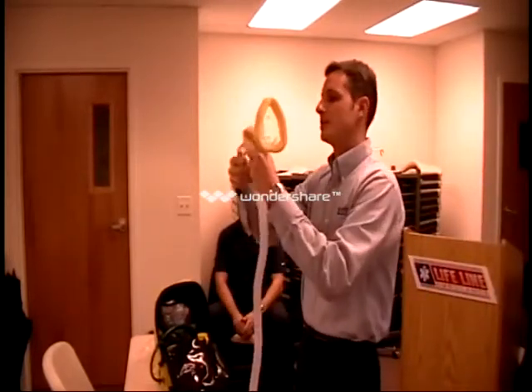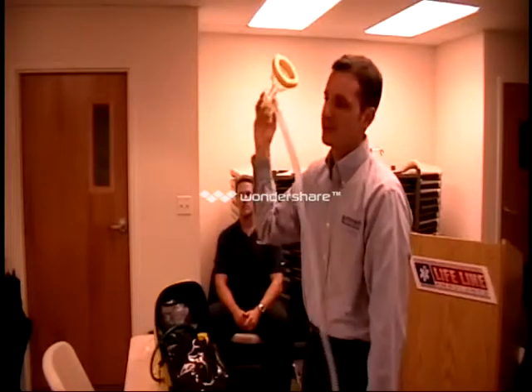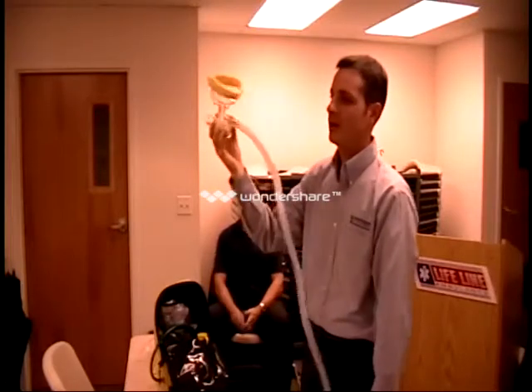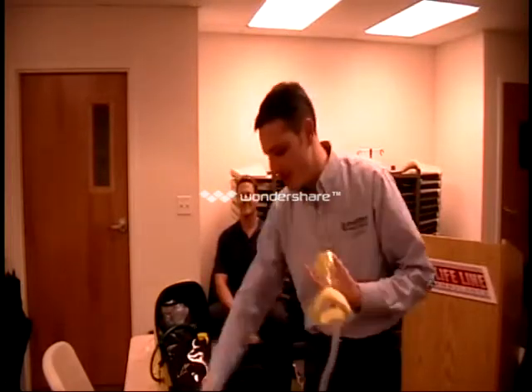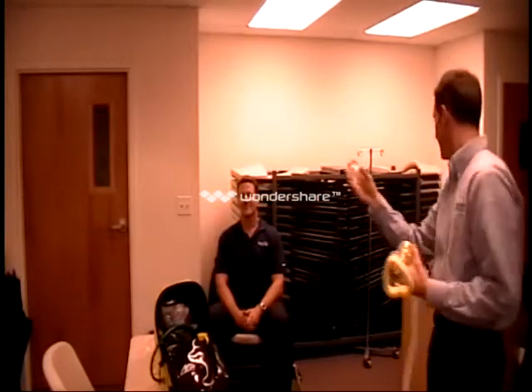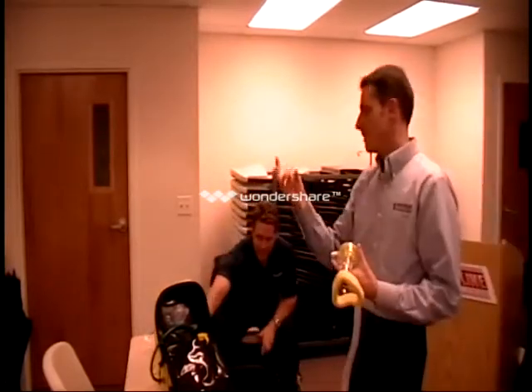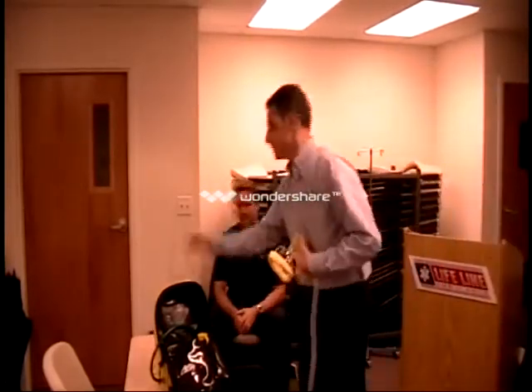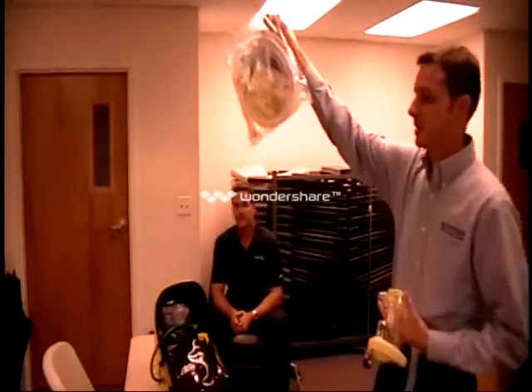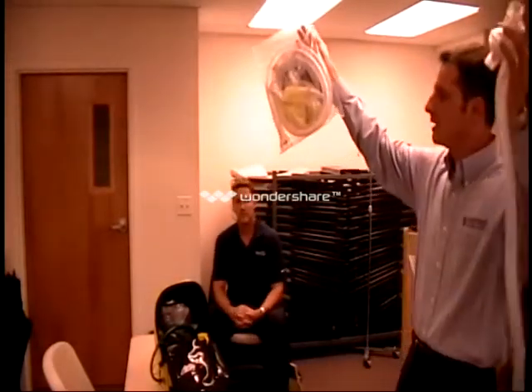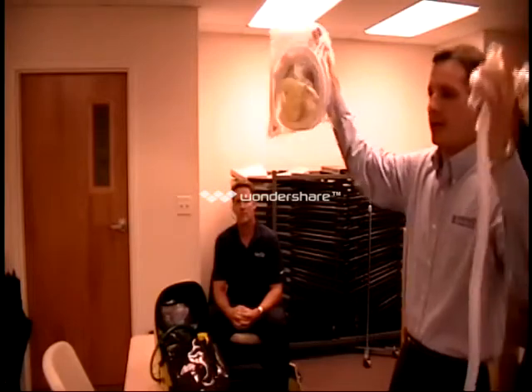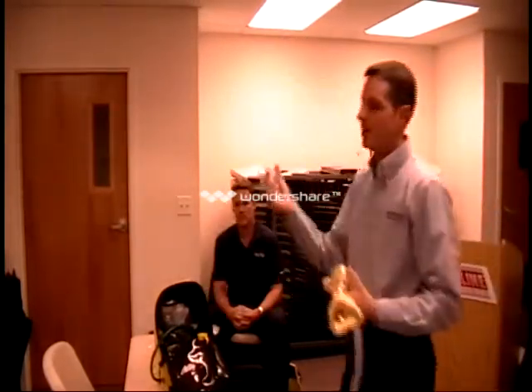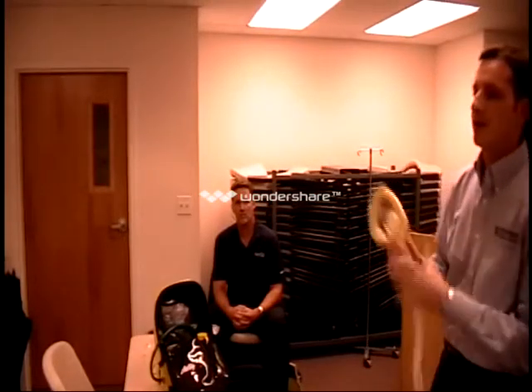This exhalation port here swivels, so you can divert what that patient's breathing out away from you, or at your partner if you're not getting along with them at the time. But no, in all seriousness, in each kit that the circuit comes in, this is your disposable portion: mask, circuit, headgear, and HEPA filter. Each one of these bags has a HEPA filter floating around in there. Make sure you grab that HEPA filter, your N95 right here, and put it right on the exhalation port here.